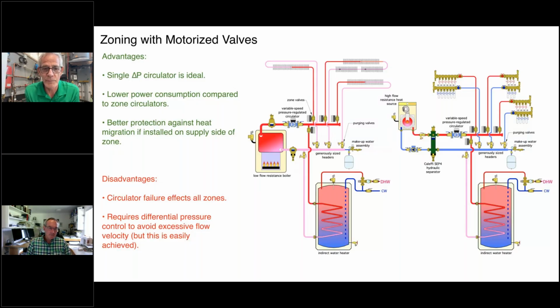They think, well, the pressure gauge on the discharge of my pump is going up. I guess the zone valve is, mm-hmm. But I think a good way to explain it is that the momentum or the flow going through there is what you're trying to close the door off against with the zone valve. Yeah, you literally can think of the water moving through the circuit as mechanical kinetic energy. The mass and the velocity are going to be the same all through the circuit, assuming the same pipe size. The mass flow rate has got to be the same, and the velocity, assuming the same pipe size, would be the same too.